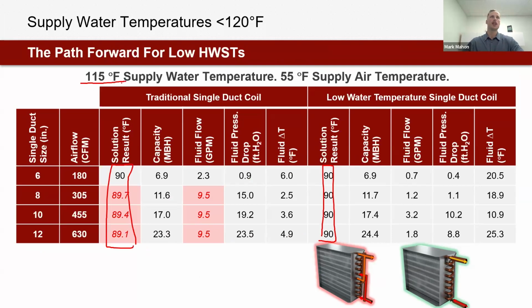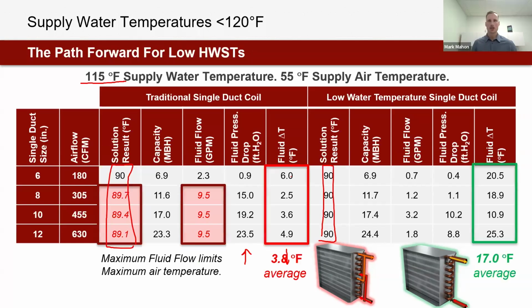We have 115 degree supply water temperature, so even a little bit more aggressive. And that discussion of coil saturation that we just had, with a traditional single duct coil, we reach full coil saturation at this design condition. We can see we're pushing as much GPM through this coil as we possibly can. Our fluid pressure drop is astronomical, which we do not love. And our fluid delta T is absolutely tiny, which is terrible for the boiler. The new low water temperature coil is going to operate much better with a much larger delta T. So we've shifted from 3.8 to 17. Our fluid flow rates have greatly reduced from up to 9.5 and 10 down to 1, 2, to 3, very typical. And our fluid pressure drop is also, because of that lower GPM, at a much more manageable condition.